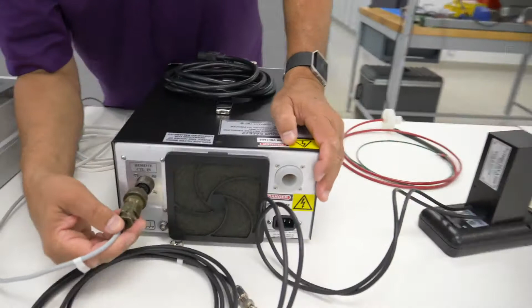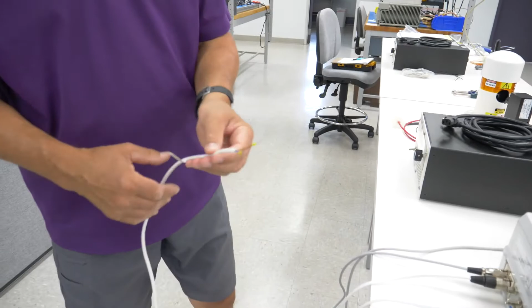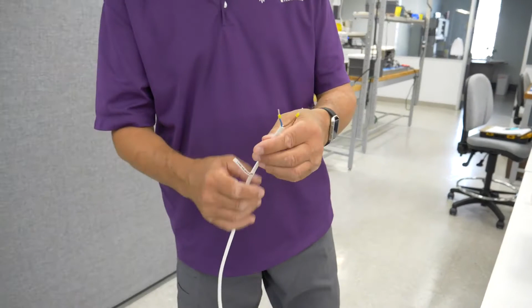Lamp reject cable. This is a 3-pin, special audio cable with a protection against any accidental removal. And this is a simple cable that offers a contact from the electronic switch inside of this controller in the case we have a bad lamp that needs to be rejected. It uses a solenoid switch that will be activated and will push out the lamp to the appropriate container. So this is just simple electronic contacts here.